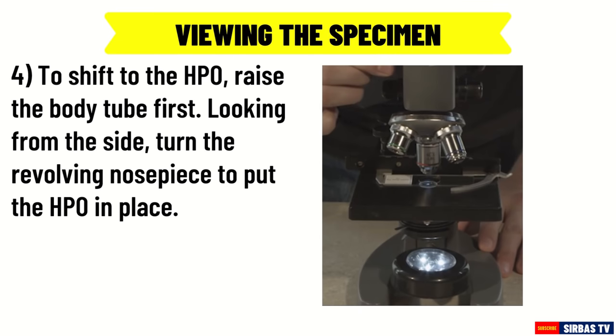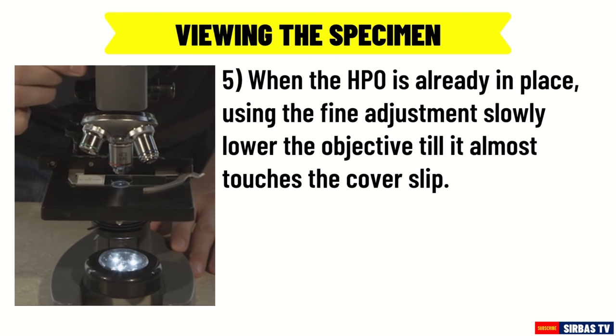To shift to the high power objective, raise the body tube first. Looking from the side, turn the revolving nosepiece to put the high power objective in place. You must watch from the side when changing objectives because objectives are of different lengths — this prevents accidental crashing of the objectives into the slide and breakage of an objective lens, slide, or coverslip. When the high power objective is in place, use the fine adjustment to slowly lower the objective until it almost touches the coverslip. Then, looking through the eyepiece, turn the fine adjustment until you see the clearest image. The fine adjustment knob should only be used with the high power objective because the high power objective is longer and can easily crash into the coverslip and slide.